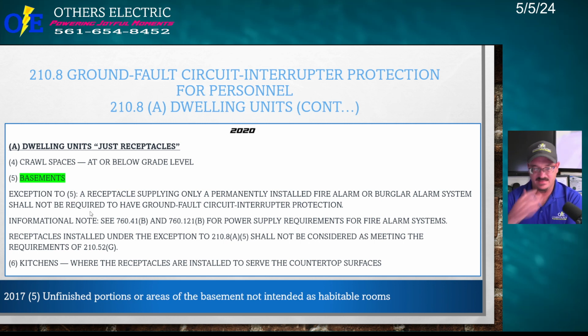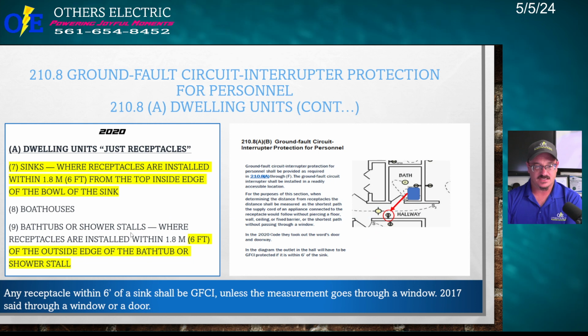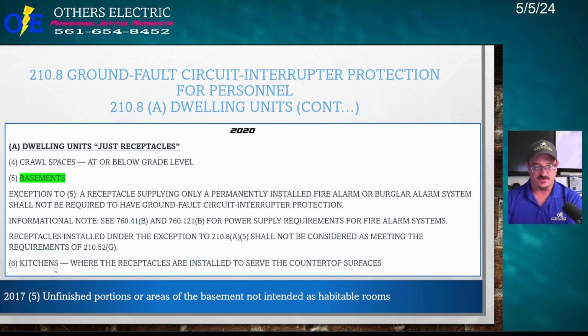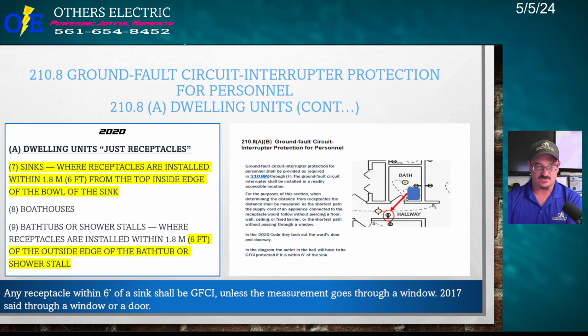Okay, the informational note, kitchens. The circuits that are required in the kitchens didn't change. These are just the receptacles. What needs to be GFI protected? That's what we're talking about. That's what 210.8 is all about. Here's this one. In sinks, where receptacles are installed within 6 foot from the top inside edge of the bowl of the sink, this didn't change. This has always been the same.